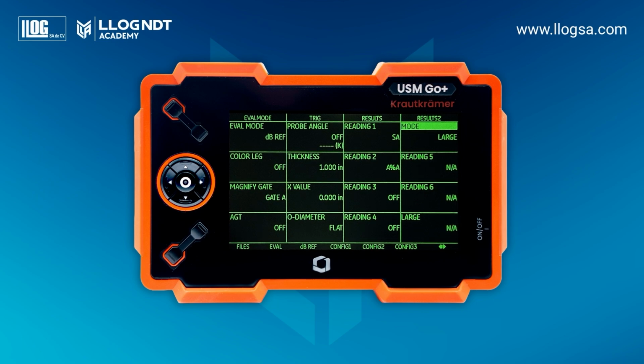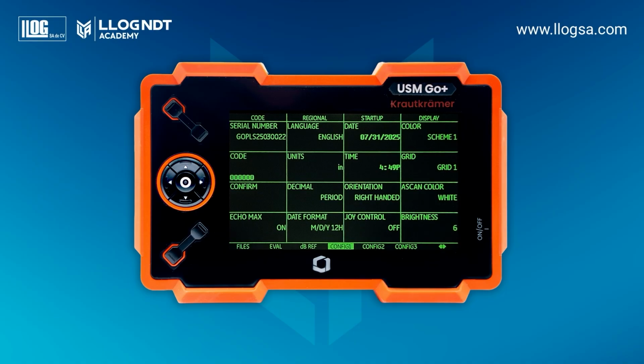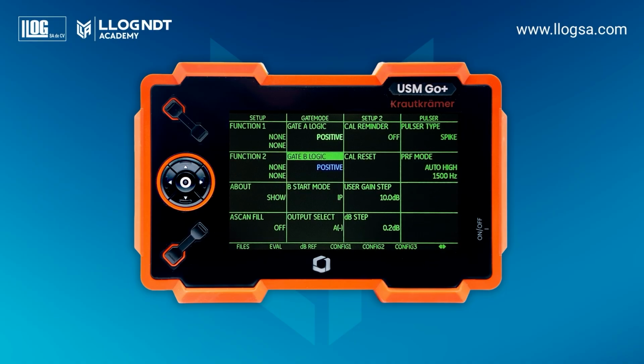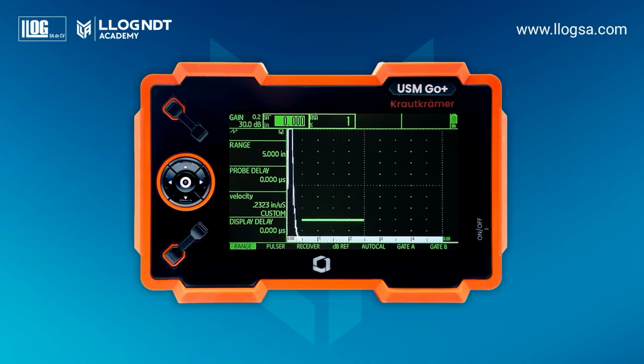Large readings mode on, and Gate B deactivated. It is important to mention that the values of these and other functions will depend on the test conditions, the type of material, and the thickness of the component to be inspected, among other variables. Therefore, the configuration and adjustments of the instrument may vary.